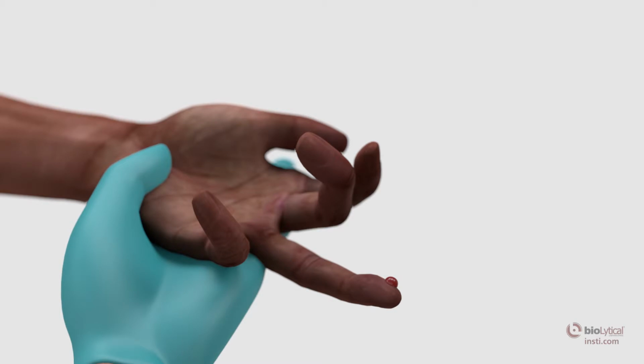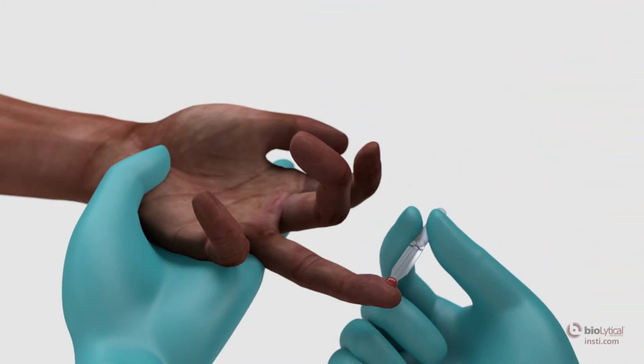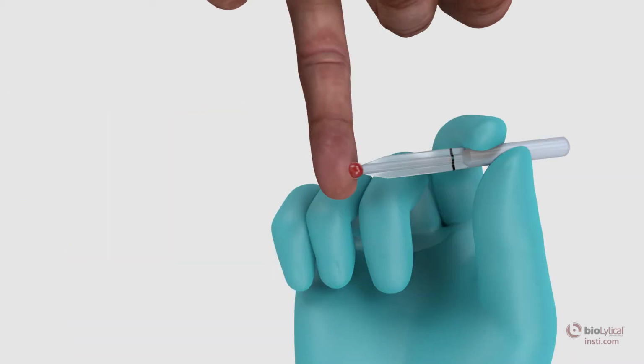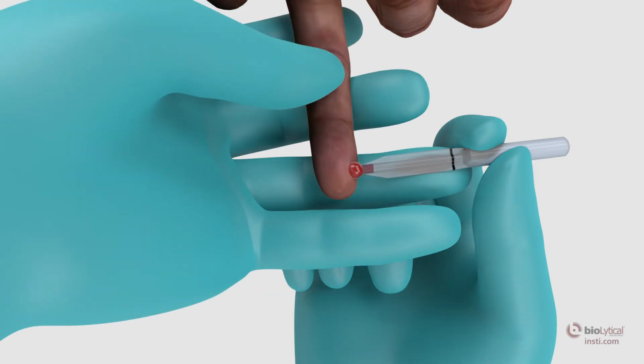Filling of the capillary pipette is automatic. Do not squeeze the bulb while sampling. Maintain this position until the flow of the sample has reached the fill line and stopped. With INSTI, the first drop of blood does not need to be wiped. Hold the pipette horizontally and carefully touch the tip of the pipette to the large round bead of blood. Hold horizontally and gently, being mindful not to cover the pin-sized hole on the 50 microliters fill line.